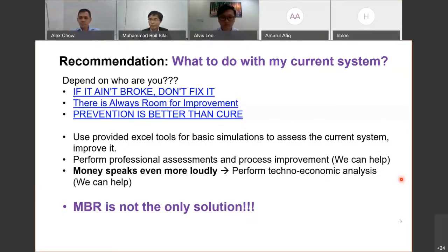So it really depends. So can it be done? Yeah, the answer is yes. It can be done, but it depends on the design. We can help you to design a system that is bubble free, of course. If you use a standardized MBR and the wastewater contains high surfactants, and the biodegradation doesn't reach, for example, a TOC level of less than 50, most likely you will have surfactants in the end.